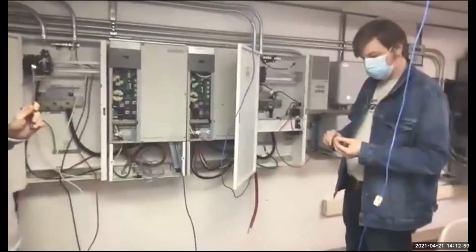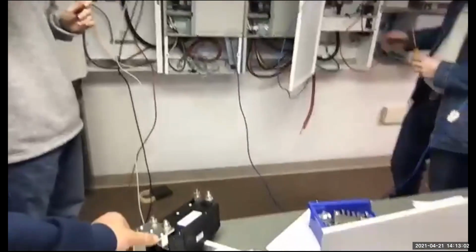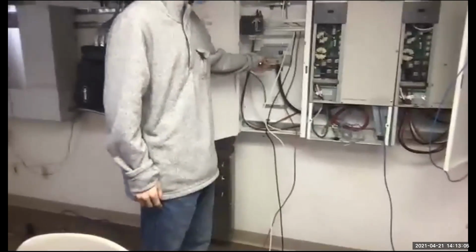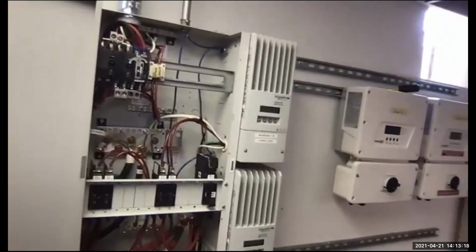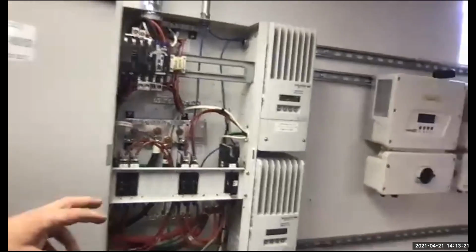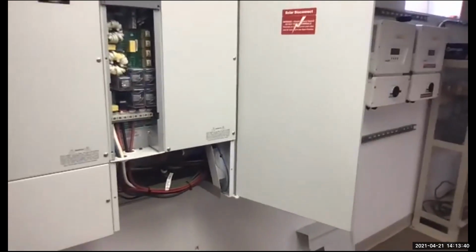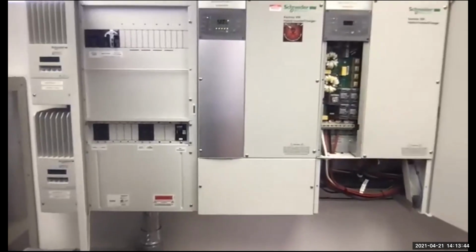And then we don't have to have like 5 250 volt breakers. Mhm. We have a bus bar. Then a change I did make, I attached this onto here. So, is that the right area, or is... No, not necessarily. Come over here. Well, let's verify. So, you're okay. I didn't say you're wrong. I said not necessarily. I just looked at how Patrick's already set up, so I was like, well, that's all right. That's why we have this. Yeah. Let's just go over this. I went over this with them. We know you don't have any batteries yet. Mhm. So you don't have a battery cable coming over. So one of those cables coming over in this trough through this pipe is a positive or a negative cable coming from these batteries that you do not have. Yeah.